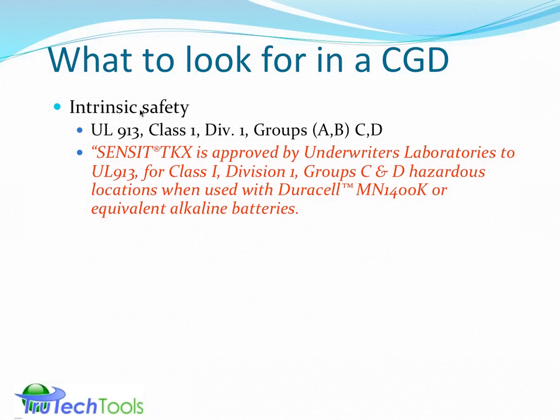So this is just to give you what it looks like from one of the manufacturer's literature. This is lifted right from the instruction manual for the SENSIT TKX, which is one of the really popular leak detectors that we sell here at TruTech Tools. It talks about the UL 913, Class 1, Division 1, Group C and D, in hazardous locations when used with a Duracell MN1400K or equivalent alkaline battery. That's a very interesting comment. We talked about design, maintenance, service, the way you use it. It's been tested to comply with this kind of battery. Other batteries may not have the same kind of compliance rating. So again, if you want to maintain your intrinsic safety, you have to follow to the letter what the manufacturer asks you to do with the product, because your usage, the batteries you use, the service you use, the way you use it is all part of the design of this intrinsic safety concept.